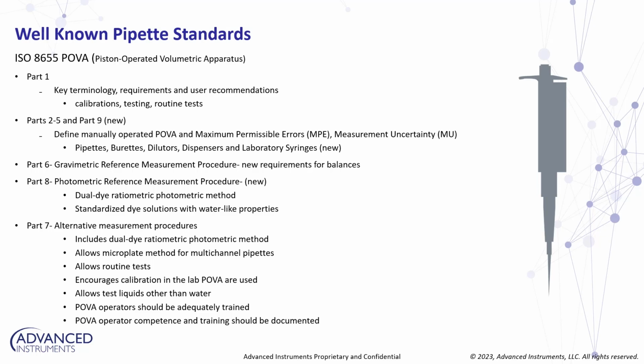Parts 2 through 5 and Part 9, which is brand new, address manually operated POVA and their maximum permissible errors and allowable measurement uncertainty for pipettes, burettes, diluters, and dispensers. And in Part 9 again, which is new, laboratory syringes are also now included.